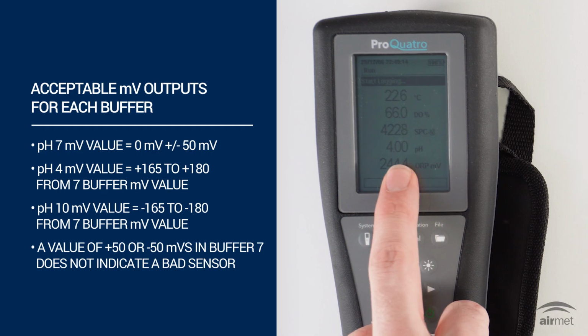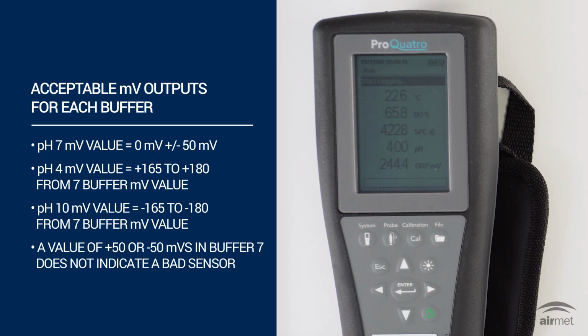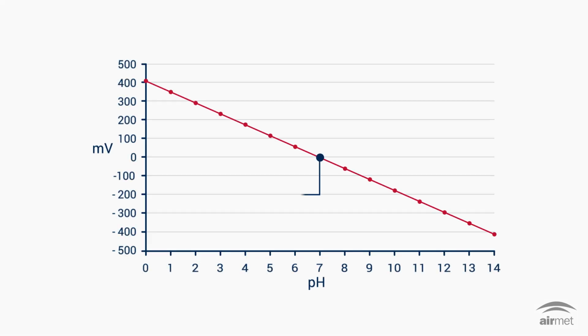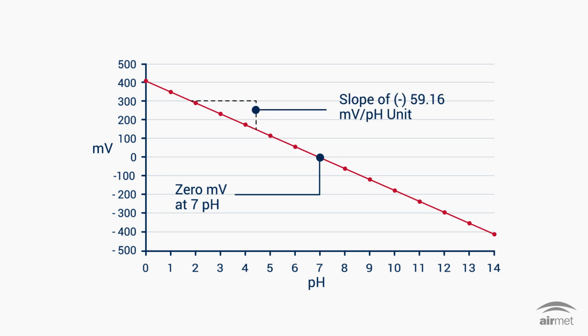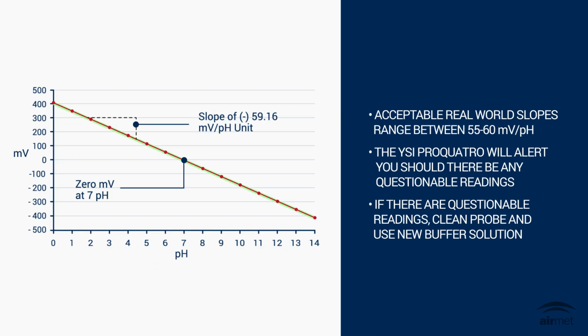Record the pH millivolts for each calibration point. The acceptable millivolt output for each buffer solution are shown here. The ideal slope for 25 degrees Celsius is around 59.16 millivolts per pH unit. This is 100% of theoretical. Acceptable real-world slopes range between 55 to 60 millivolts per pH, which is around 93 to 102%.